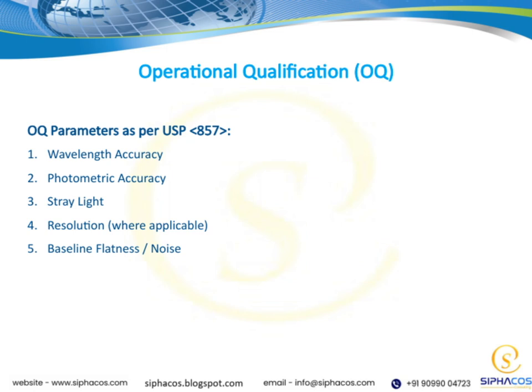Finally, we have baseline flatness and noise. These parameters help us evaluate the stability of the instrument's baseline signal, ensuring there are no fluctuations or noise that could affect the results. All of these parameters work together to confirm that our instrument is operating within the required specifications, supporting the overall quality and accuracy of our analytical methods.